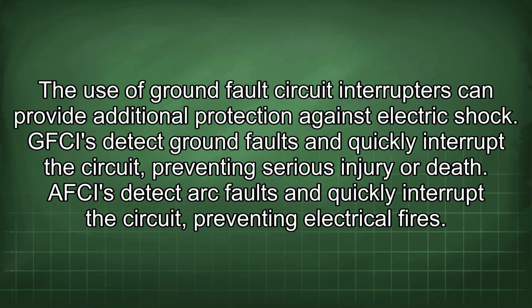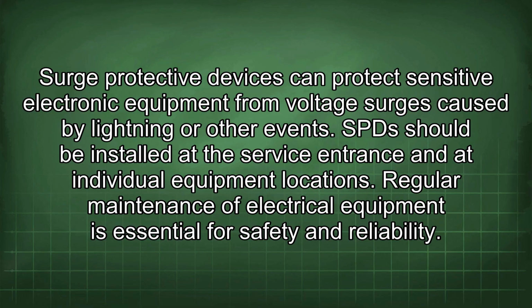The use of ground fault circuit interrupters can provide additional protection against electric shock. GFCIs detect ground faults and quickly interrupt the circuit, preventing serious injury or death. AFCIs detect arc faults and quickly interrupt the circuit, preventing electrical fires. Surge protective devices can protect sensitive electronic equipment from voltage surges caused by lightning or other events. SPDs should be installed at the service entrance and at individual equipment locations.